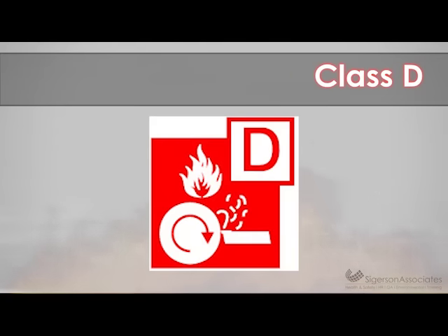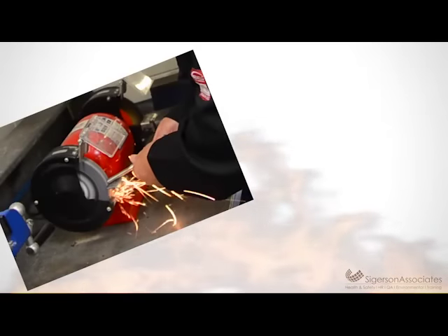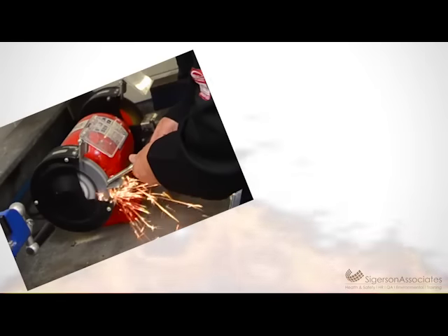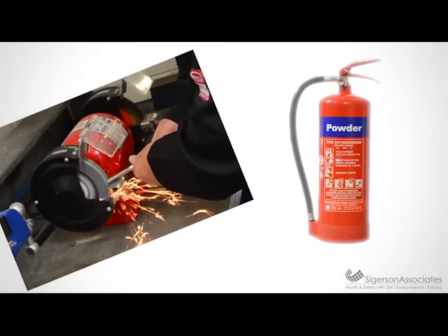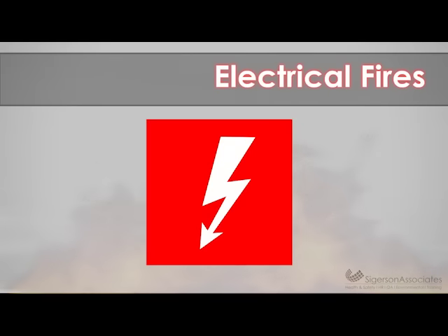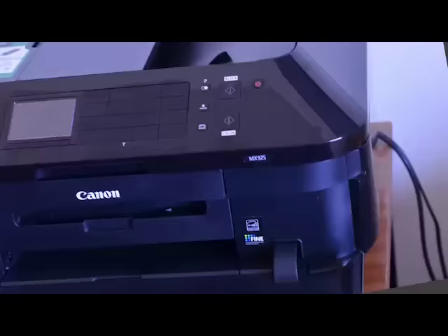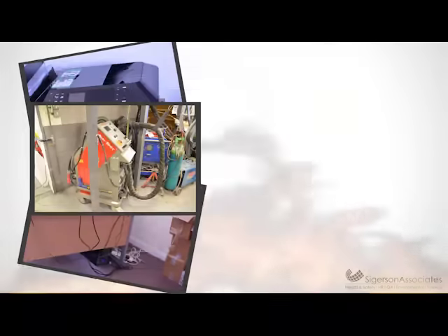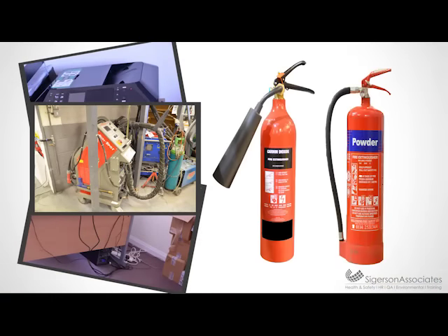Class D. Fires involving burning metals such as aluminium, magnesium and titanium. These can be tackled using dry powder extinguishers. Fires involving electrical equipment such as photocopiers, fax machines, computers and electrical tools. These can be tackled using CO2 or dry powder extinguishers. However, dry powder may leave a residue that can damage electrical equipment.